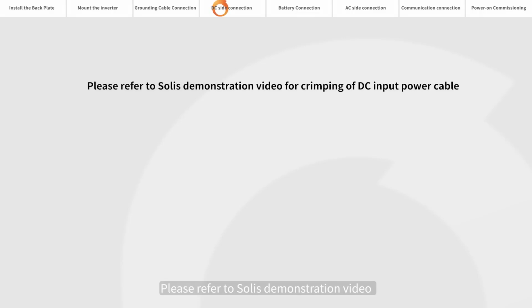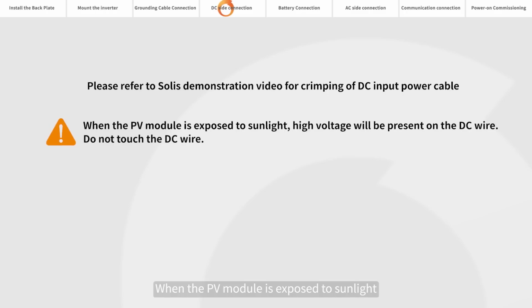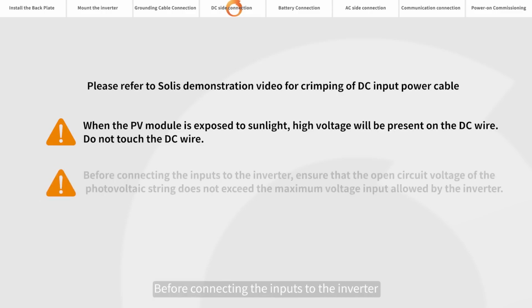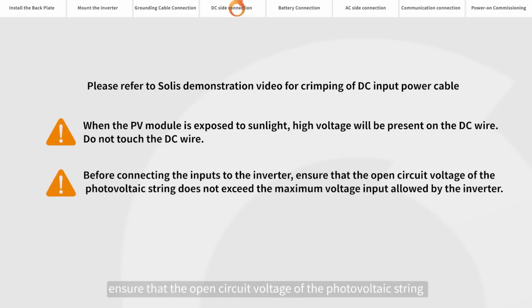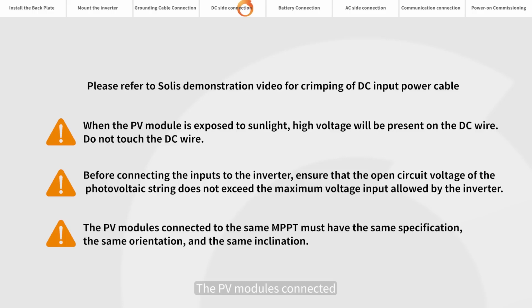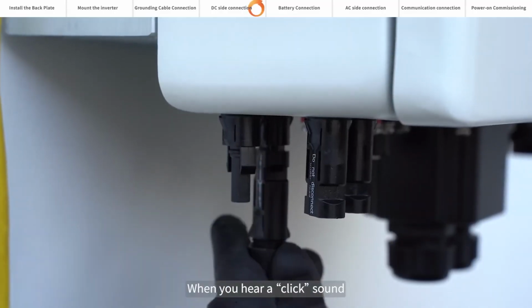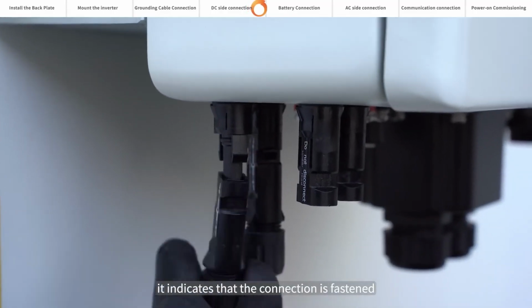Please refer to the Solis demonstration video for crimping of the DC input power cable. When the PV module is exposed to sunlight, high voltage will be present on the DC wire. Do not touch the DC wire before connecting the inputs to the inverter. Ensure that the open circuit voltage of the photovoltaic string does not exceed the maximum voltage input allowed by the inverter. The PV modules connected to the same MPPT must have the same specification, the same orientation, and the same inclination. When you hear a click sound, it indicates that the connection is fastened.